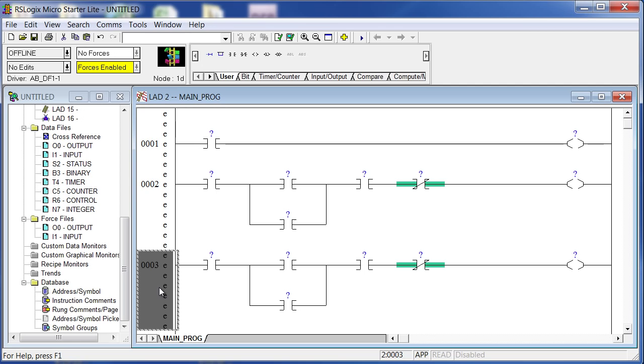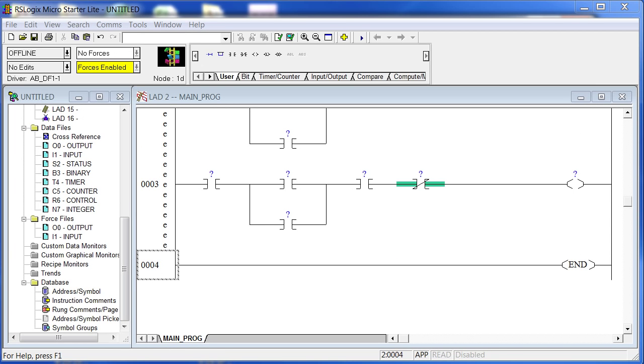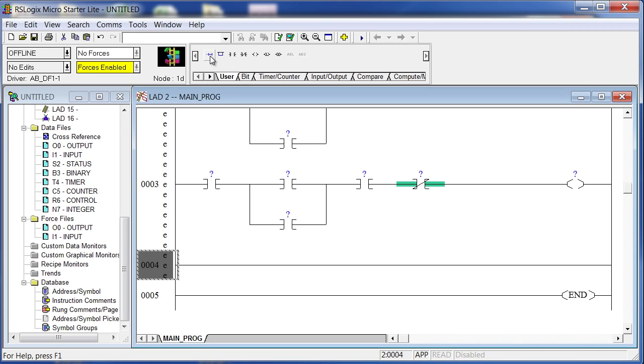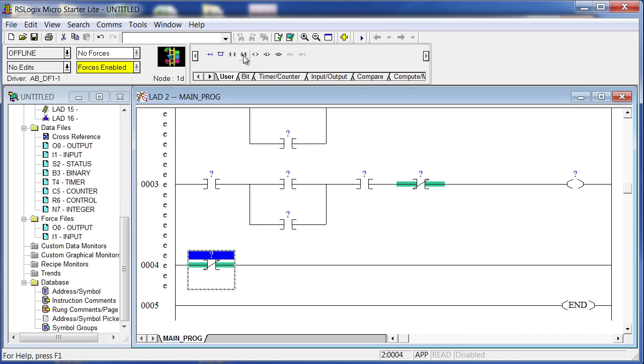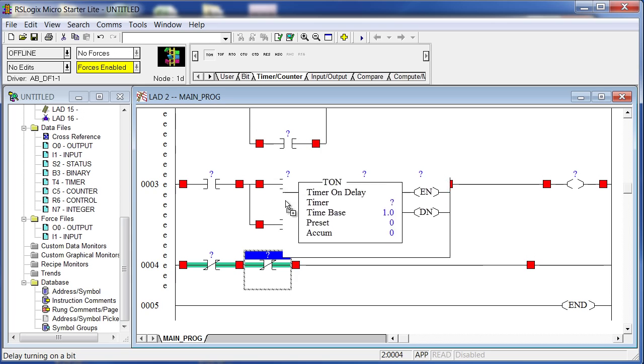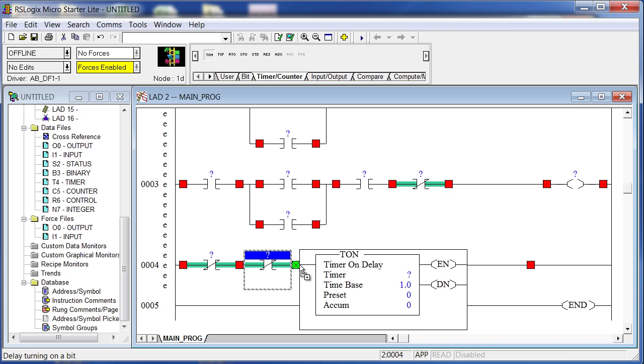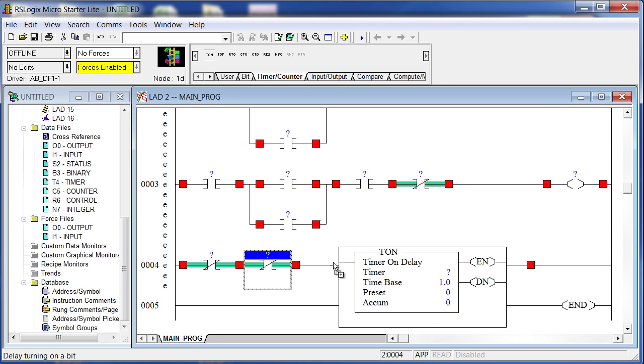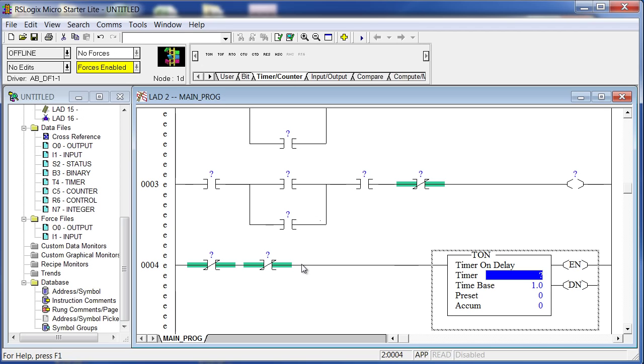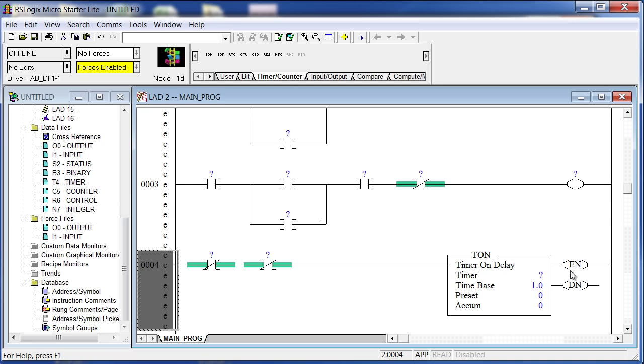We're going to add a couple more Examine If On instructions, branch around them, and add another Examine If On, another Examine If On, an Examine If Off, and what looks like a relay coil. I can copy this with Ctrl+C and paste with Ctrl+V. Now the electrical timer — we won't be able to make the logical timer look exactly like the diagram, but we'll keep the same order. We'll drop down a rung and need two Examine If Off instructions plus a timer.